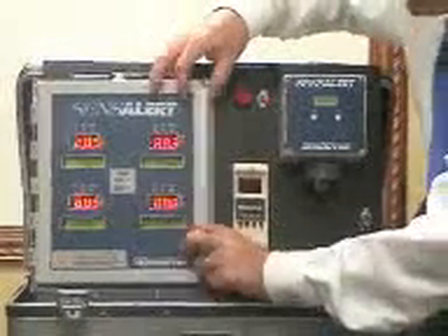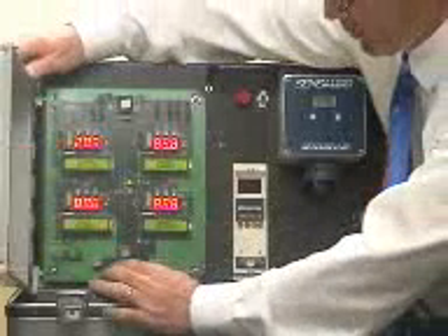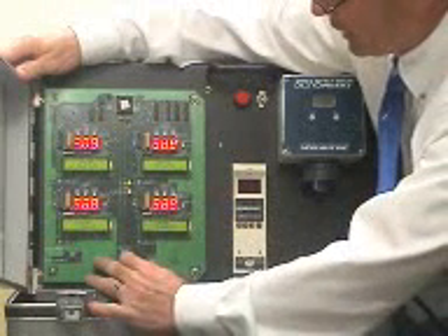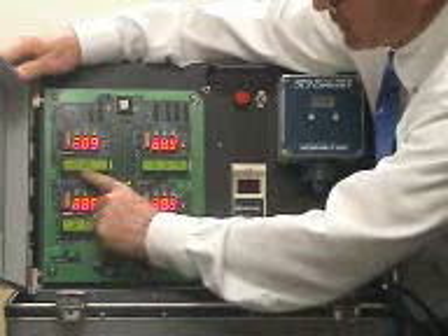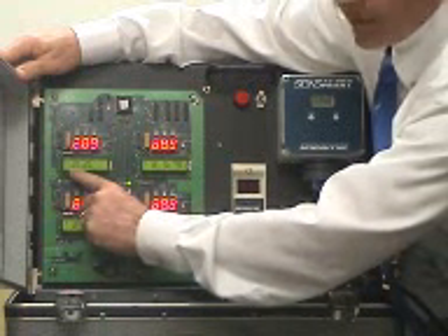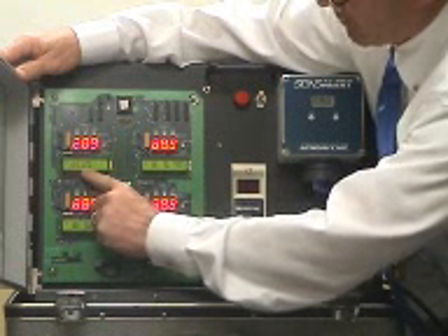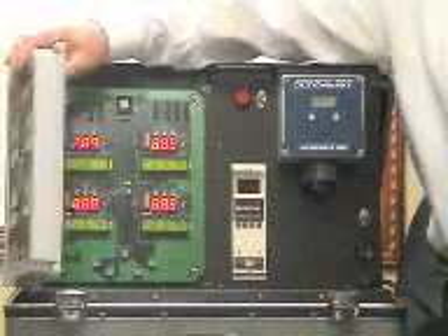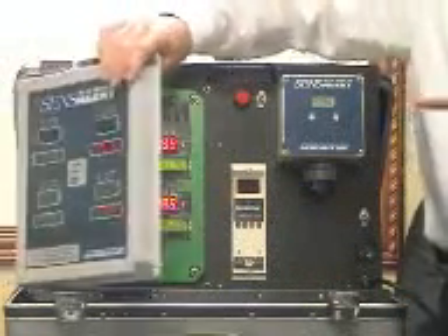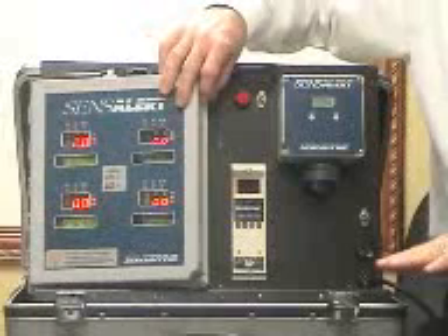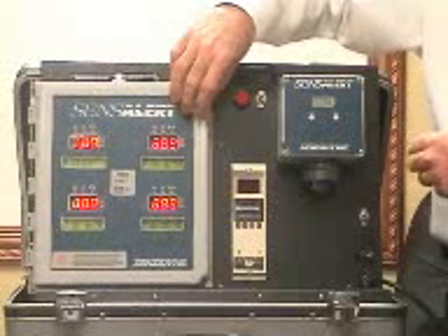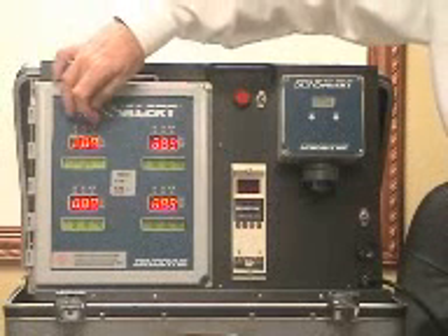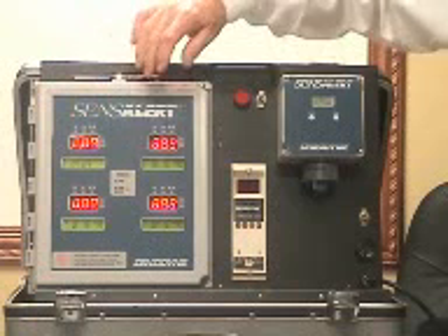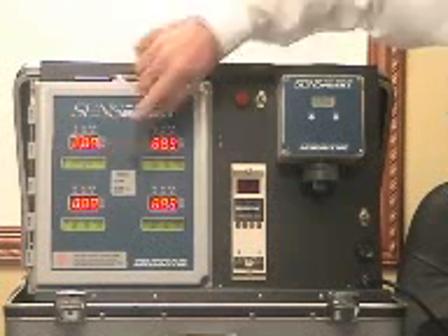To see the alarm settings, you press the next button, and it displays the 2 alarm settings. A low alarm of 19.5 and a high alarm of 23. The oxygen has a deficiency alarm, where if the reading of oxygen goes down, it trips. And it also has an enrichment alarm. If the reading goes above 20.9, I think the alarm setting was 23.